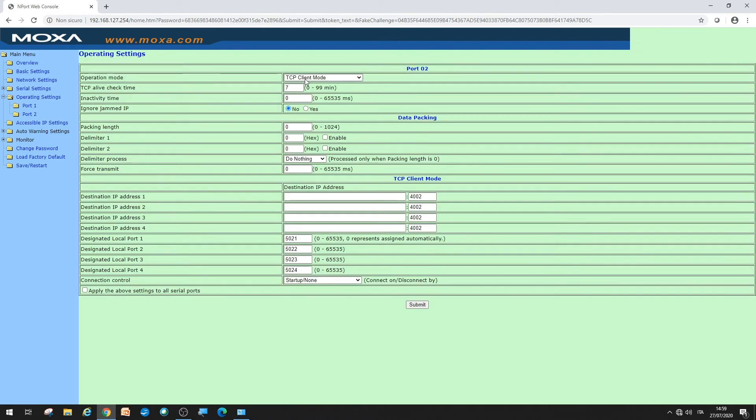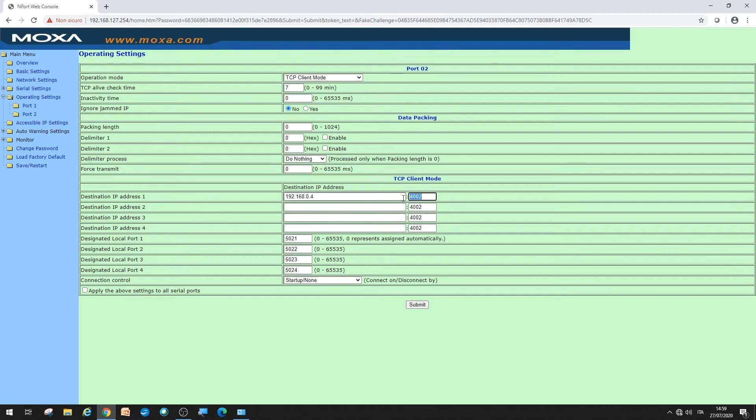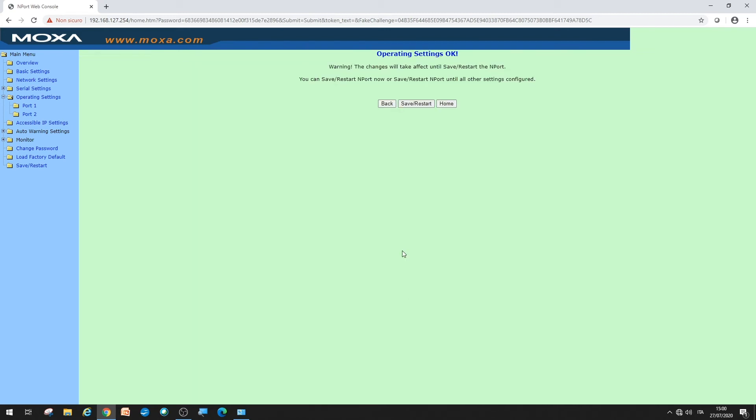You must specify the IP address of the gateway data logger EXC GA-01 in the fields that are shown. In this case, it is 192.168.0.4. The value of the TCP port must be 1000. Confirm with submit and then save and restart.